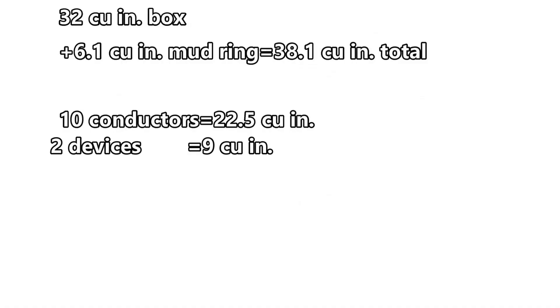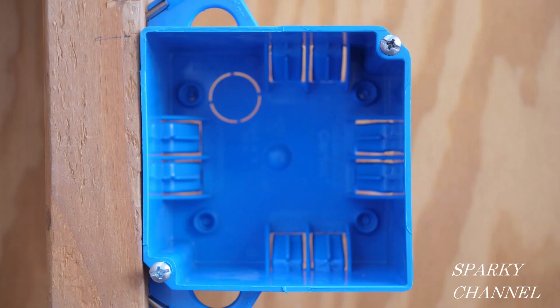So we add the two devices to the 10 conductors and now we have 31.5 cubic inches. How about the integral box clamps? Some people feel that they should be part of the calculations for box fill. So let's call these internal clamps and see what the code has to say about them.